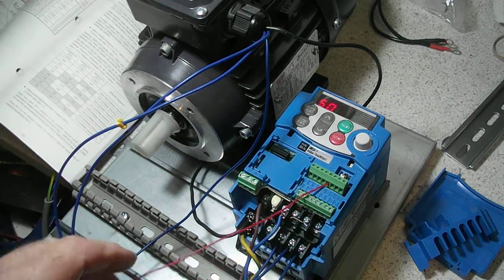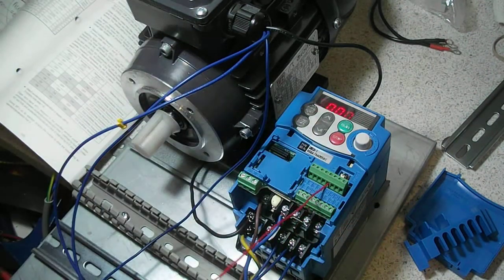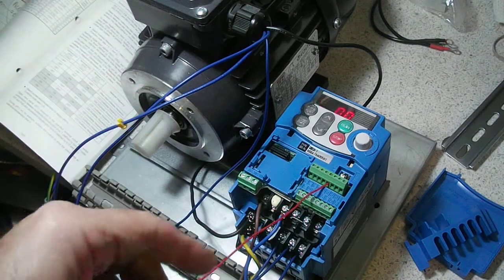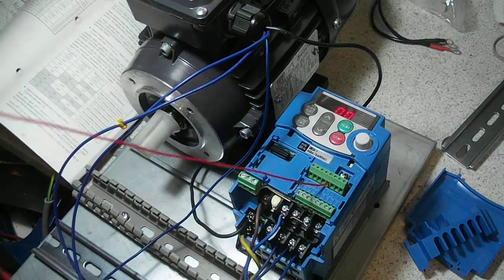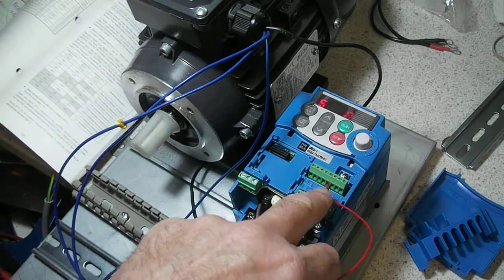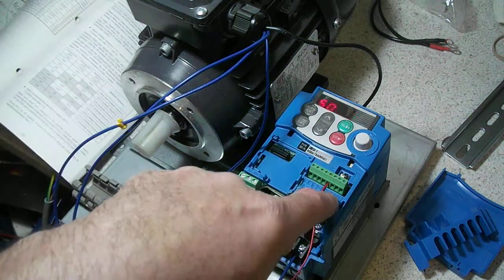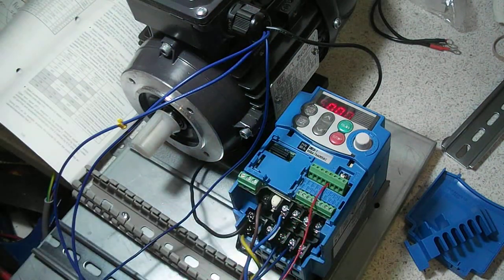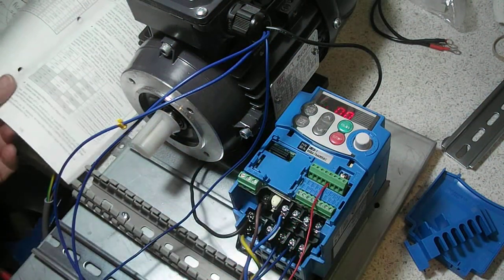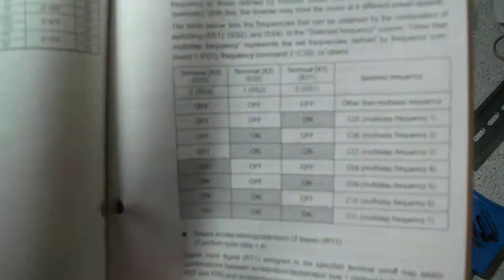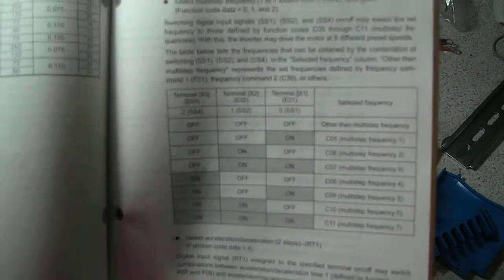Now on these inverters there is a 24 volt power supply inside them, so there's 24 volts available on this PLC terminal here, and you can use that to pulse these other three here: X1, X2, and X3. With this particular model, you can have up to seven different frequency settings from the combination of those three inputs.